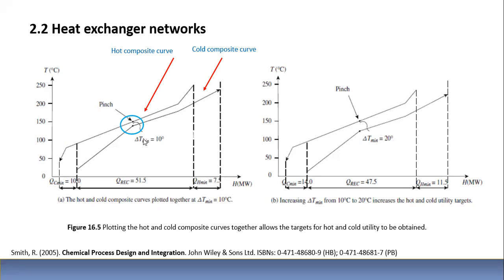Okay, so far, so good. This is from 10 degrees Celsius. If we move this hot composite curve to the left, making this space bigger, then we can have a difference of 20 instead of 10. But as you will notice, the minimum amount of energy required will be bigger, 11.5 instead of 7.5. And the amount of energy that needs to be absorbed now, instead of 10, is 14. And the energy being recovered, instead of 51.5 megawatts, is now just 47. So there is a price to pay.